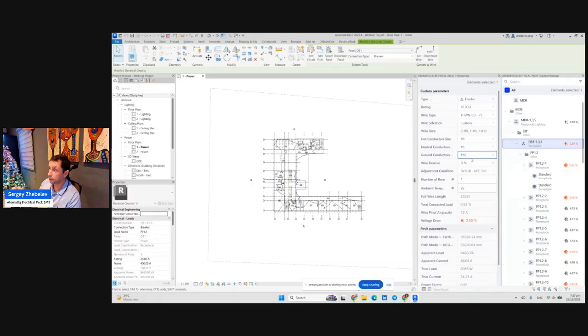But if something goes wrong, you get notifications from us. Let's go back to auto mode. We have reserve - you can set a wire reserve, and we calculate full wire length using this number. Again, adjustment conditions: wires can be in conduit, in cable tray, above the ceiling - different situations, different conditions, and we try to handle them all.